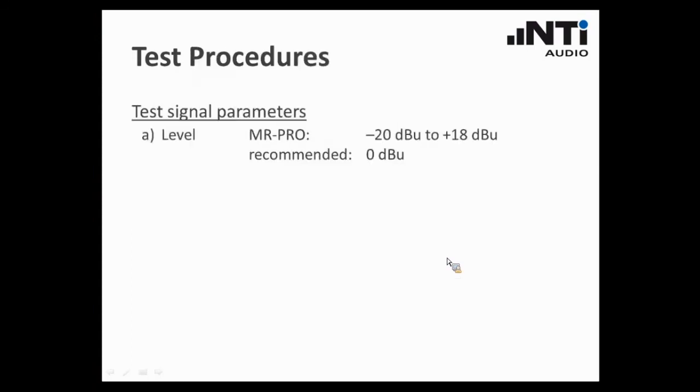Second, talking about the test parameters. Now referring to the MR-PRO signal generator from NTI-Audio, you have a certain range where you can adjust the output voltage of the test instrument. We recommend to start at 0 dBu, which is, if you are not so acquainted with this unit, it is in a range of about 1 V, a little bit less, but it is a good starting voltage. Second, talking about the frequency, we would recommend to start at about 1 kHz, but as mentioned before, because the impedance and the power of the system depends on the frequency, you may also adjust other frequencies in this range from 30 Hz to 10 kHz.